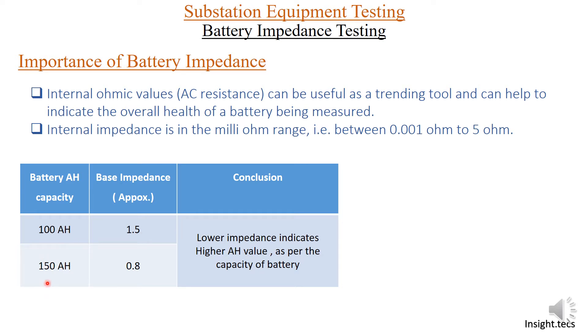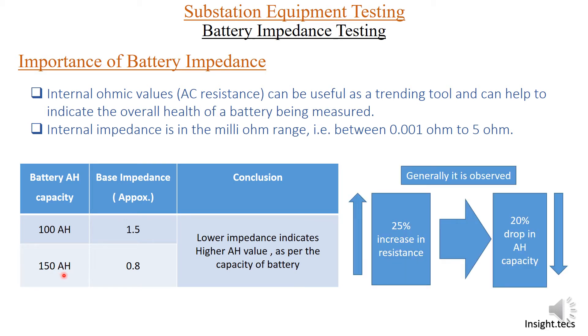If the ampere hour capacity increases — say it is 150 Ah — then the impedance decreases. So we conclude that lower impedance indicates higher ampere hour value. Generally it is observed that when there is a 25 percent increase in resistance, there is a 20 percent drop in Ah capacity. So we always have to check the impedance values — lower impedance is better for the Ah capacity of the battery.